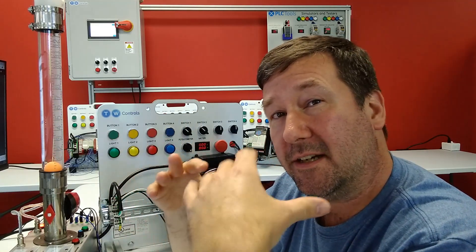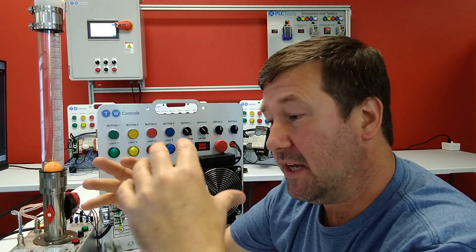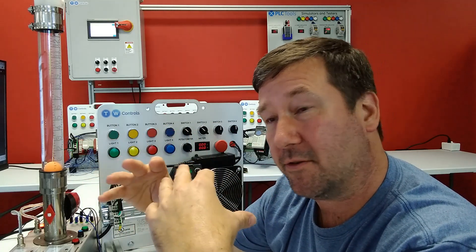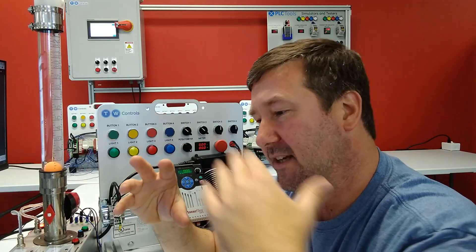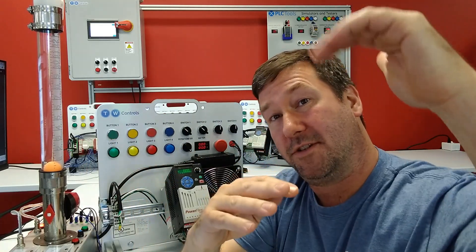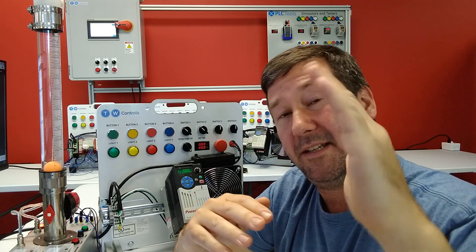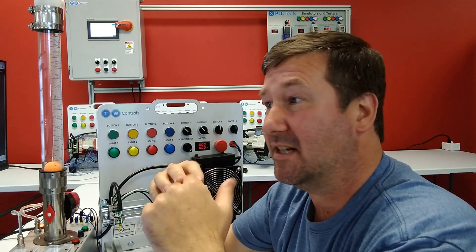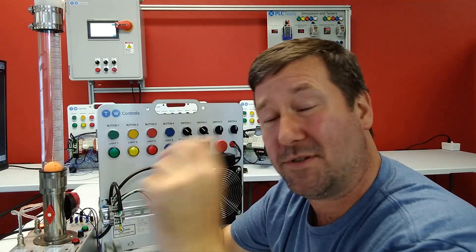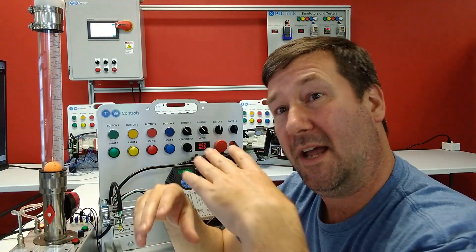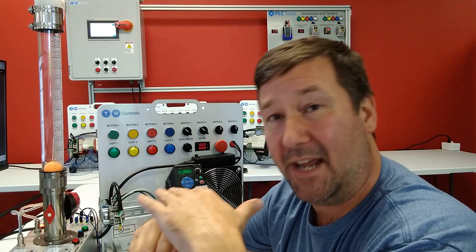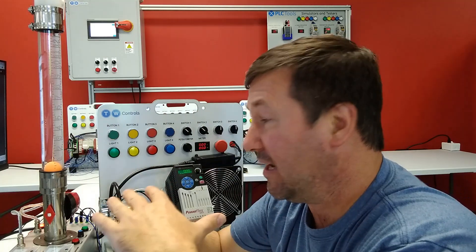So hope that helps you understand the relationship between the proportional and the integral. And what I would recommend here is really play with this. Set the integral at something and then play with the proportional to see how it affects whether it overshoots, whether it undershoots, whether we get an oscillation. Also, let's make sure we understand that there is no true proportional control when we're using this particular equation. If you set your proportional at something and your integral and your derivative at zero, you will get no action out of your PID output.